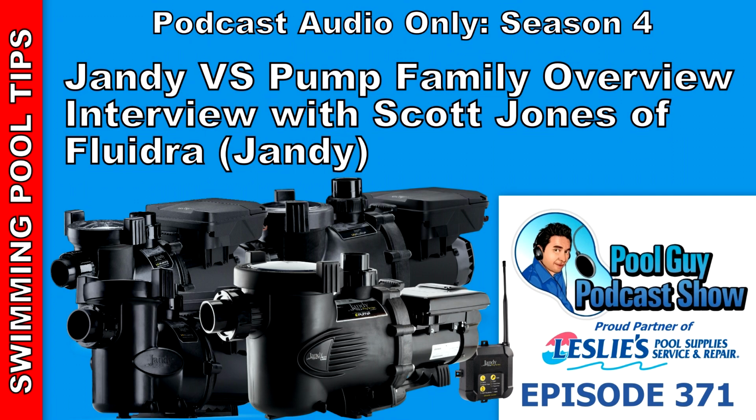So this is going to be maybe a little too technical for some people, but I'm going to use the term derating. Variable speed pumps on the market that operate on dual voltage, most of them typically, when you get above 3,000 RPM, the pump is generating more heat in the components in the variable speed drive. Over 3,000 RPM, it's going to be generating too much heat. So the firmware in the pump limits the speed at which that pump can operate. If you're running 230 volts, you're going to get full performance. If you're running 115 volts, you will get full performance up to 3,000 RPM. Above 3,000 RPM, it basically limits itself so that you don't overheat and damage the components.